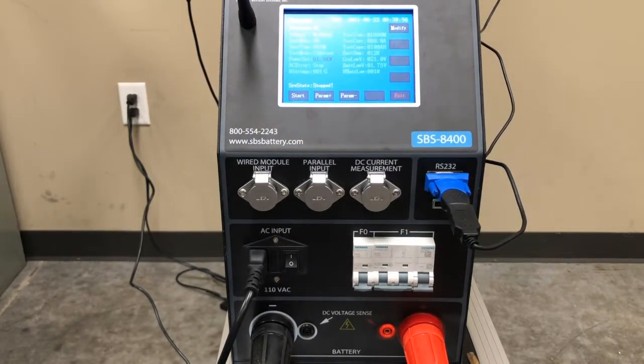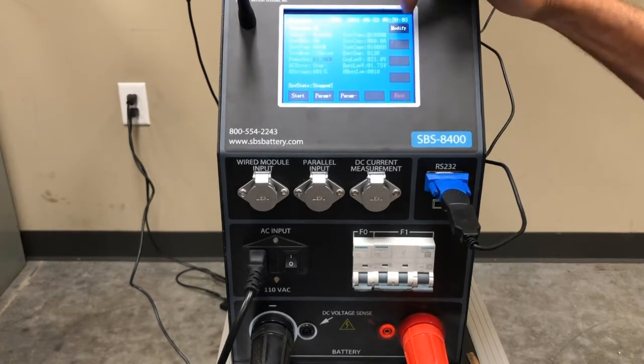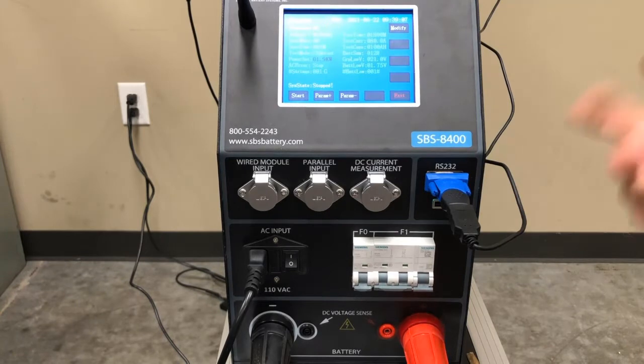So in this instance, we're going to go into parameter 1, and we're going to modify it to be the test that we will actually want to run. We're testing an HX540 high rate battery, and we're going to be doing a 1-hour test. So what we did is we went to the manufacturer's data sheet. We looked for constant current discharge rates. We found that that battery is rated to 1.75 volts per cell at 97.3 amps for 1 hour. So that's what we're going to set our test up as. Our baseline reference data is going to be 97 amps for 1 hour down to 1.75 volts per cell, 10.5 volts per battery block, 105.0 volts DC for our group low voltage shutdown.